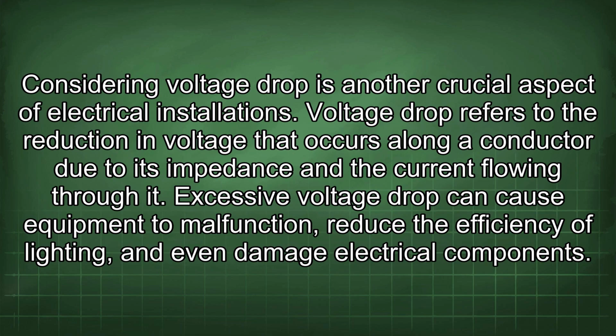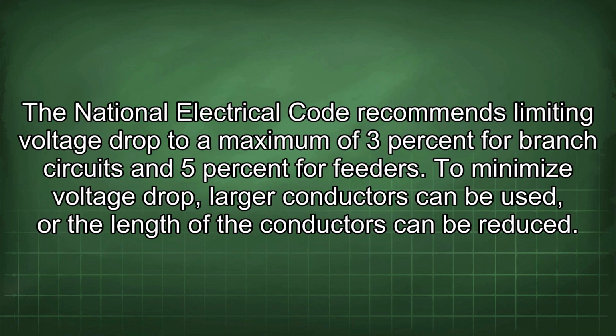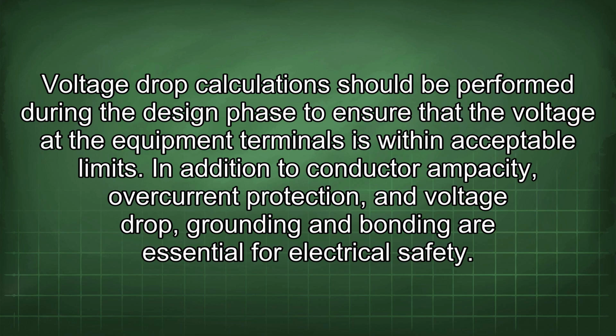Considering voltage drop is another crucial aspect of electrical installations. Voltage drop refers to the reduction in voltage that occurs along a conductor due to its impedance and the current flowing through it. Excessive voltage drop can cause equipment to malfunction, reduce the efficiency of lighting, and even damage electrical components. The National Electrical Code recommends limiting voltage drop to a maximum of 3% for branch circuits and 5% for feeders. To minimize voltage drop, larger conductors can be used, or the length of the conductors can be reduced.